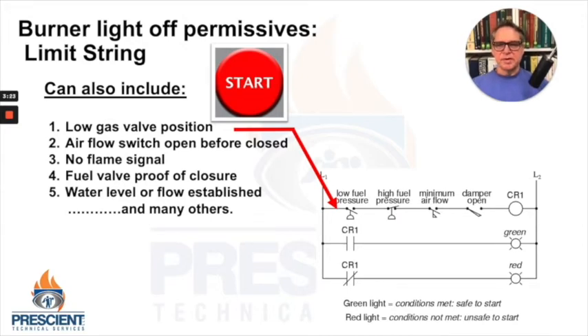Could be that there's no flame signal. Obviously a good idea to not have a flame signal before the light-off sequence. You could have fuel valve proof of closures. You could have water level types of things in boilers that need to be at some minimum position. So again, you hit the start button, the BMS looks at all the permissives, and it then would allow or permit the next step to occur if these conditions are made. So kind of working backwards, if you're troubleshooting and you hit the start button and nothing is happening, you have to look at one of these conditions to see if one of these conditions is not made or is not occurring.